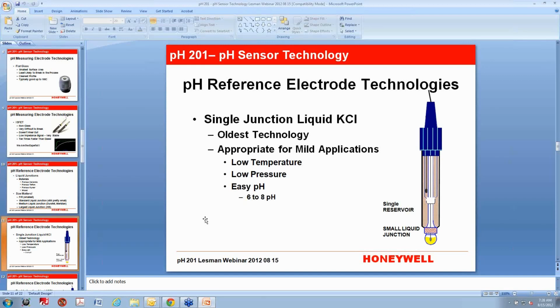The liquid technology is the oldest technology. Basically, it's just a saturated solution of potassium chloride in clean water. It's a good technology for mild applications where you don't have high temperature, you don't have high pressure, and the pH is maybe 6 to 8. The reason being, again, that your process fluid is going to want to go into and mix with the potassium chloride in the reference area of your sensor, and if it's a liquid, that's the easiest way for that to happen. So if you're in a process pH of 6 to 8 and there's nothing weird in there, no strange ionic species, you can usually get away with having a single liquid junction and a liquid potassium chloride.